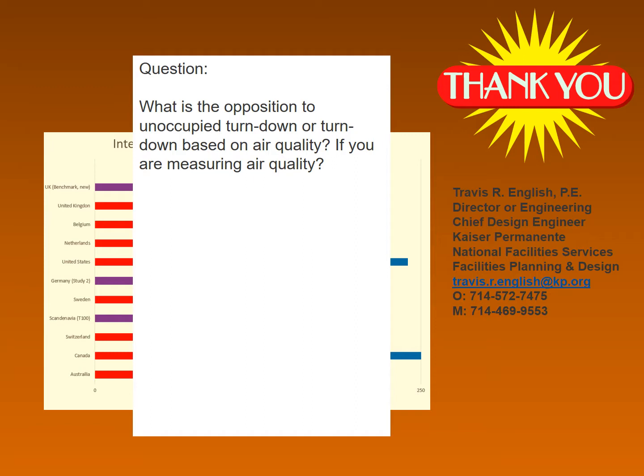One interesting thing would be if and when we rethink inpatient rooms, that could open the door to demand control ventilation. Because when you're sleeping, you don't produce very much, so a trickle of air in that room is likely going to maintain air quality just fine. But the code structure we have now doesn't allow any of those performance-based alternatives.